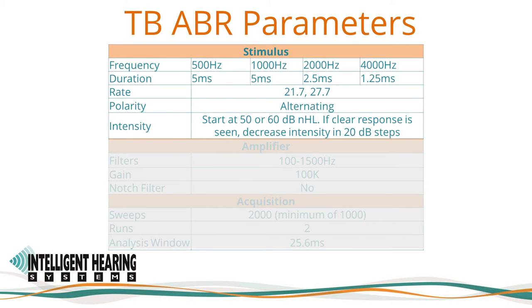We will use a 5 ms duration for the 500 and 1000 Hz tones, 2.5 ms for the 2000 Hz tone, and 1.25 ms for the 4000 Hz tone, presented at 21.7 or 27.7 per second. We use an alternating polarity for the tone bursts. Standard threshold search procedures should be employed, starting at 50 or 60 dB nHL. If a clear response is seen, decrease the intensity in 20 dB steps using an up-10 down-20 bracketing procedure to determine threshold.